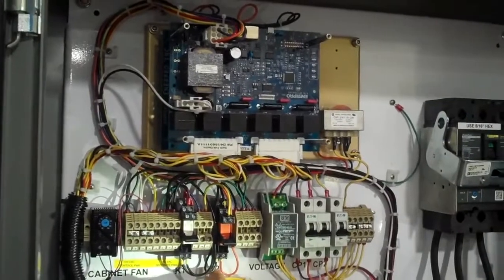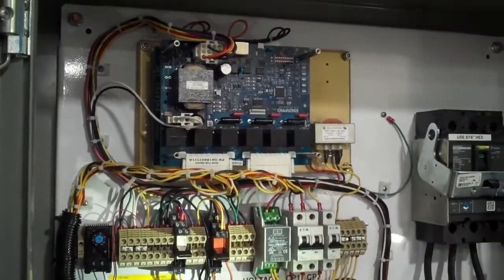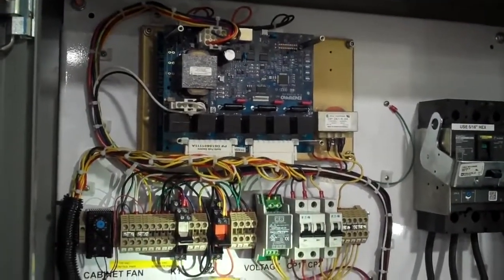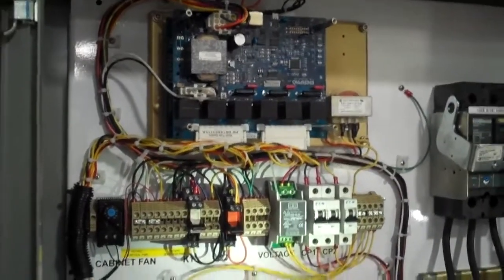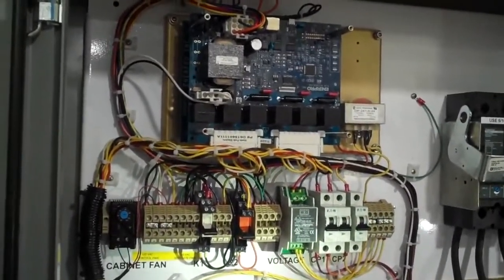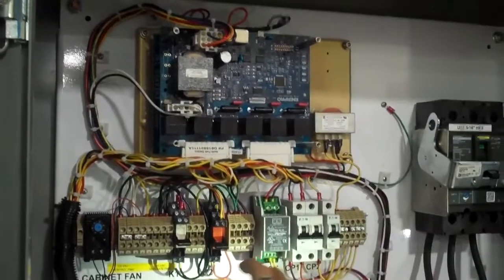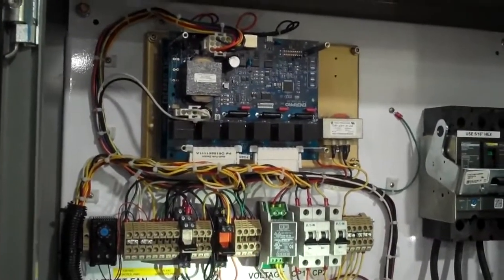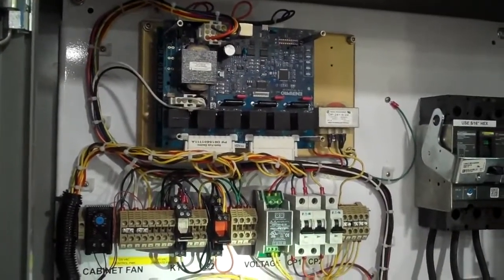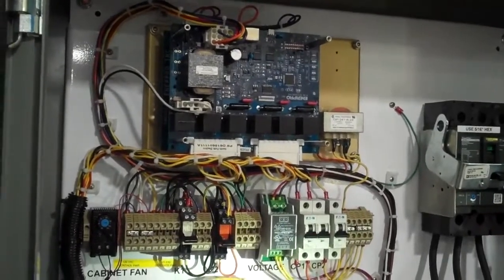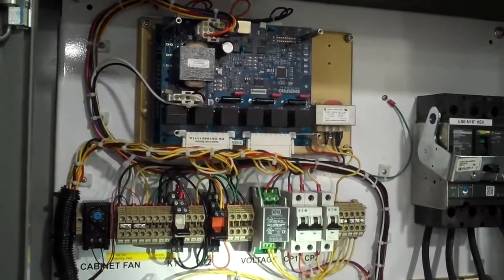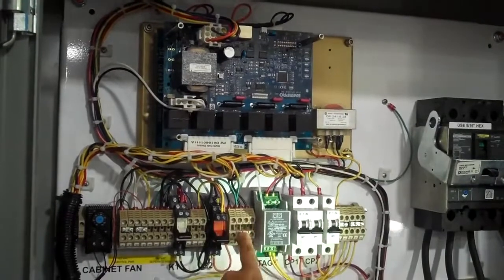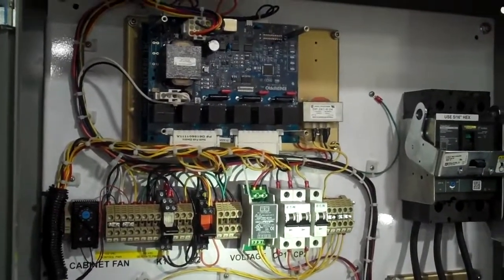Here we have a second relay, that's K2, and we have positions 11 and 12 being the enable status. Every time that this board is enabled, there will be a dry contact closure of a relay that will determine its status. Position 13 is just a convenient common.